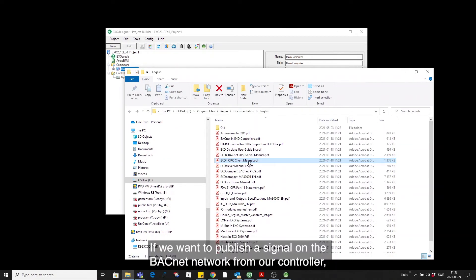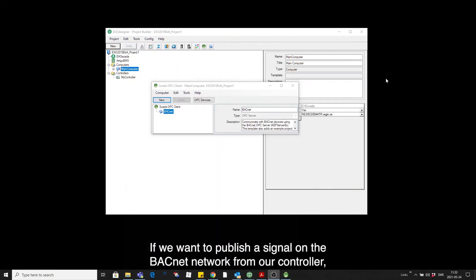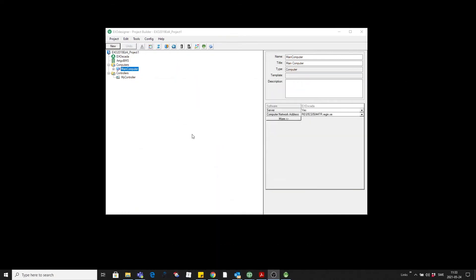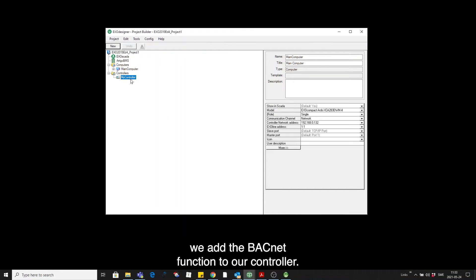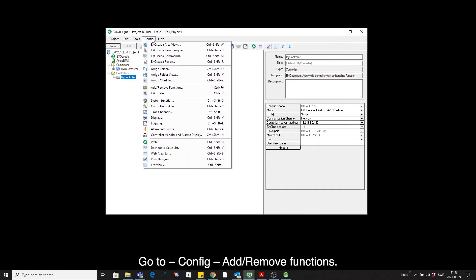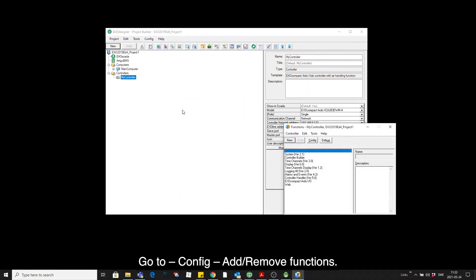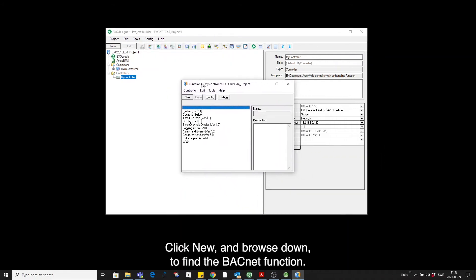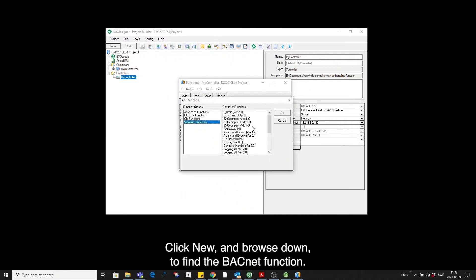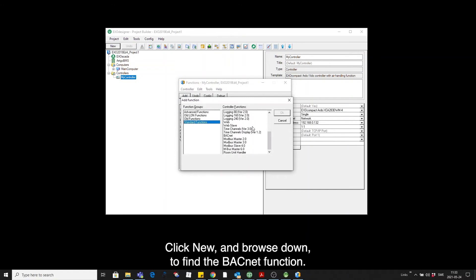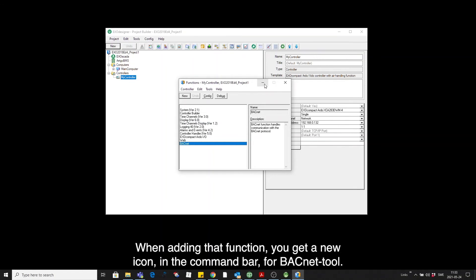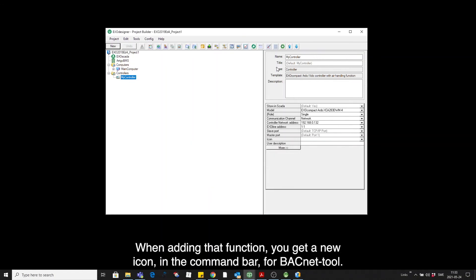If we on the other hand want to publish a signal on the BACnet network from our controller, we need to add the BACnet function to our controller. You do that by going to config, add remove functions. And if you click New and browse down here, you will find the BACnet function. And upon adding that function, you get a new icon in the command bar for BACnet tool.